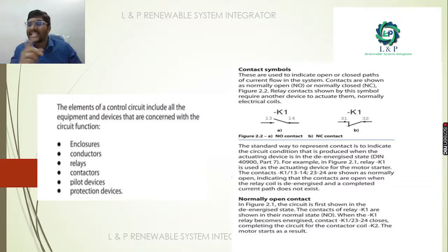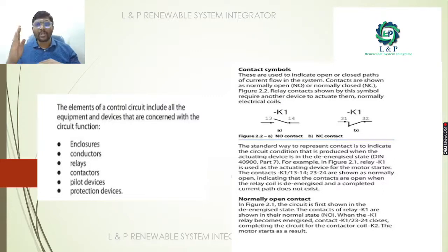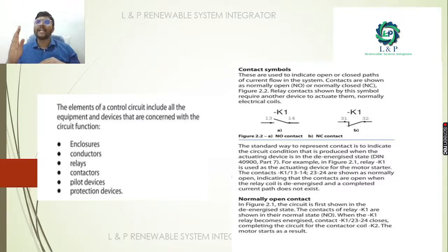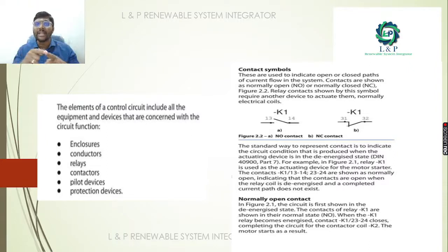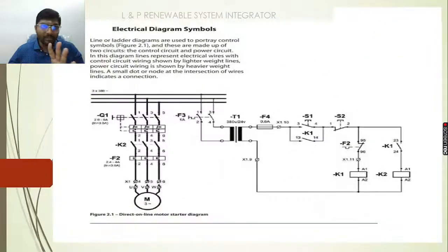The most basic contact symbols are the NO contact (normally open) and the NC contact (normally closed). For emergency conditions we typically use the NC contact. For normal switching operations, the circuit remains open. When the electric coil is energized, the contact immediately changes position from open to closed, making continuity and completing the circuit. NO and NC contacts are used in most control circuits.